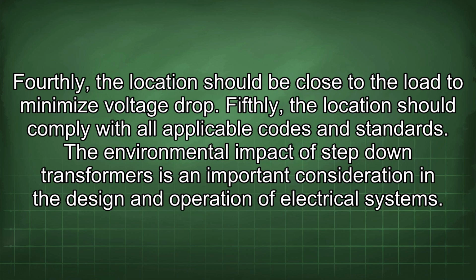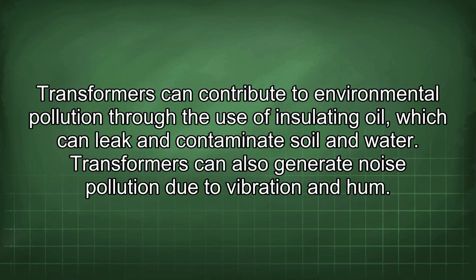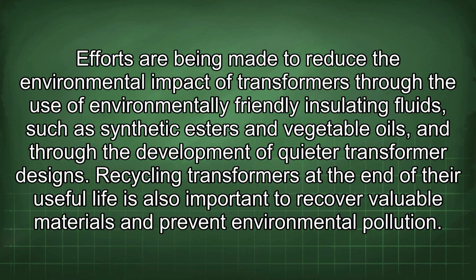The environmental impact of step-down transformers is an important consideration in the design and operation of electrical systems. Transformers can contribute to environmental pollution through the use of insulating oil, which can leak and contaminate soil and water. Transformers can also generate noise pollution due to vibration and hum. Efforts are being made to reduce the environmental impact of transformers through the use of environmentally friendly insulating fluids, such as synthetic esters and vegetable oils, and through the development of quieter transformer designs.